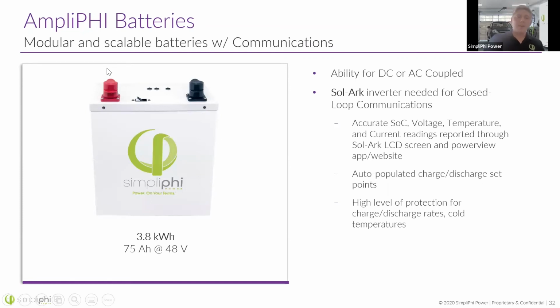Now we also are offering our newer, I would say more intelligent battery. This is the AmpliPHI battery. It's the same energy capacity of 3.8 kilowatt hours and 75 amp hours at 48 volts. However, this battery is going to intelligently communicate with the Sol-Ark inverter or the Sunny Island inverter with closed loop communications. Now again, this can be AC or DC coupled alike. But with this battery, it's not compatible with a whole wide range of equipment. For now, it's just these two inverters until we're able to test more for compatibility.